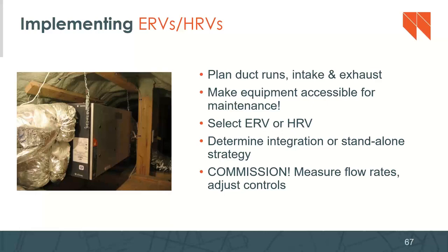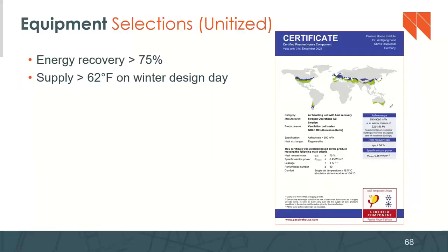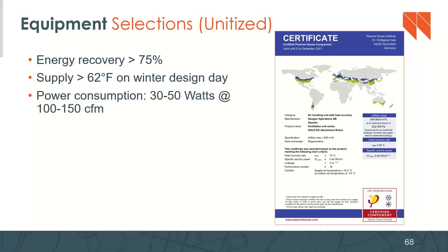Selecting the right box, the ERV or HRV, determines the integration. Is it going to be a standalone strategy? And then commission it. These are the tools to success. So for equipment, how to select stuff. For passive house, the energy recovery has got to be at least 75%. The supply for the design temperature, you want that to be greater than 62 degrees Fahrenheit for a design day in the winter. So this means you might need a duct heater, depending on how efficient your ventilator is.